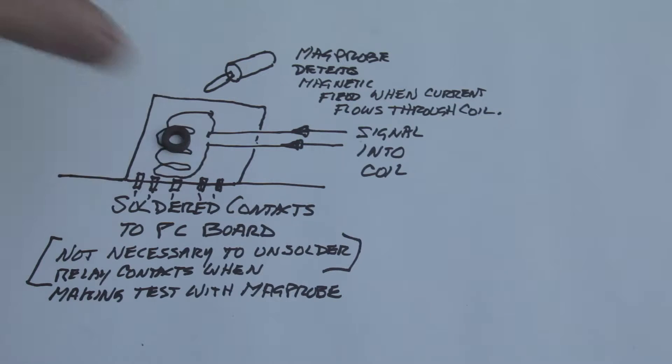So in order to make the test with a mag probe, instead of unsoldering all the contacts and pulling the relay off and going through all kinds of drastic measures, in order to do this with a mag probe you just hold the mag probe up to the coil.